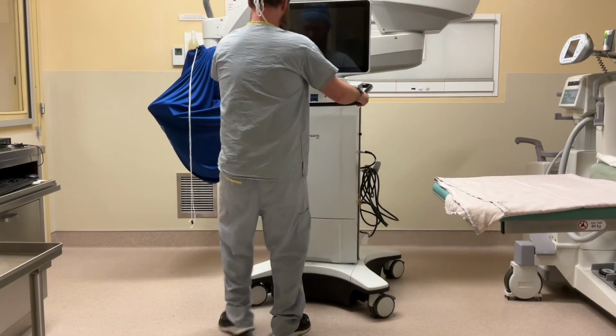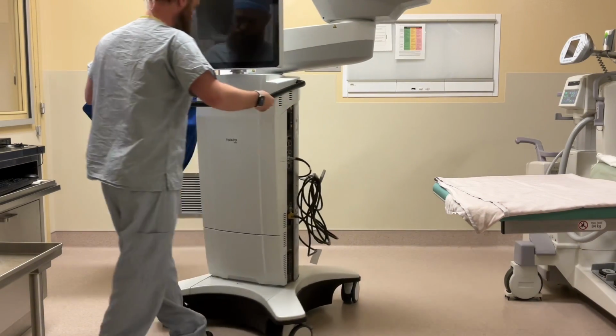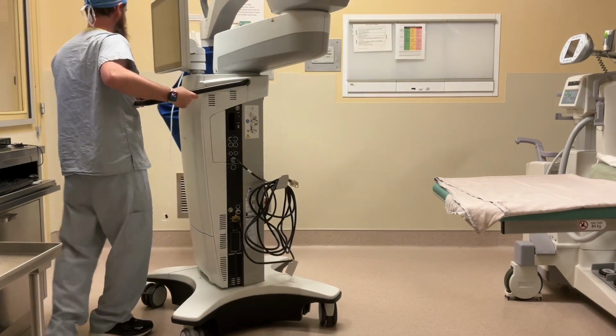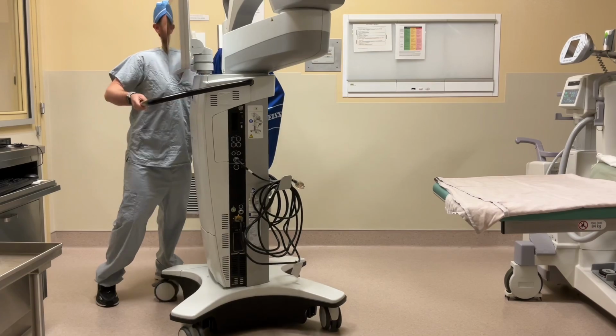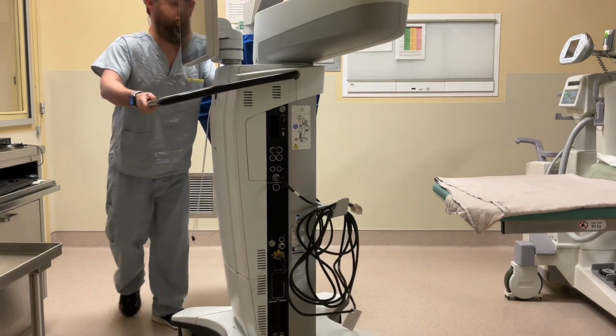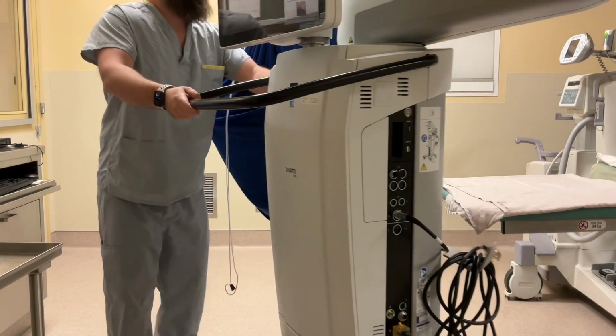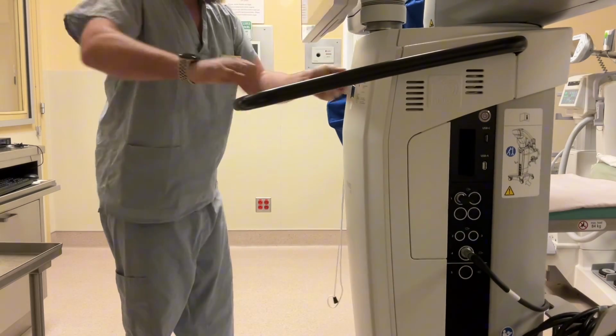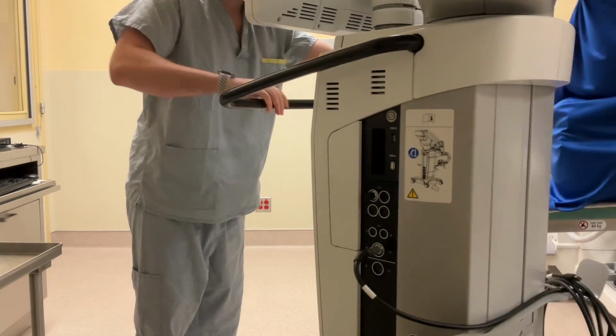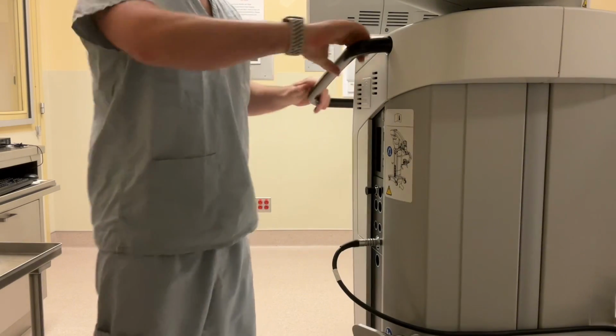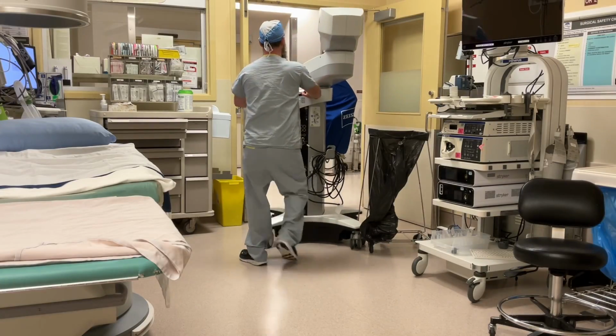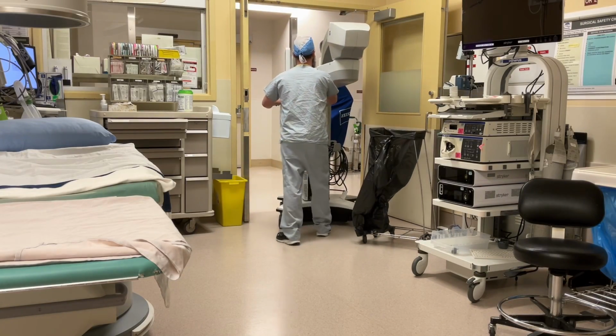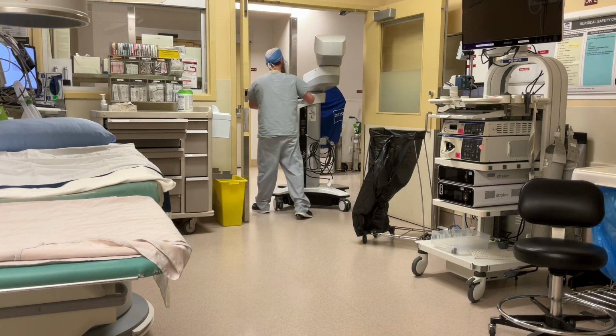When moving the microscope, use the handlebar to maneuver it around the OR. At no point should the microscope arm be moved, as this will cause damage to the brakes. If the microscope arm has to be readjusted, the microscope will need to be turned on first and then adjusted using the All Brakes button found on the hand grip. When moving the microscope from OR to OR, push the microscope from behind to see where you're going.